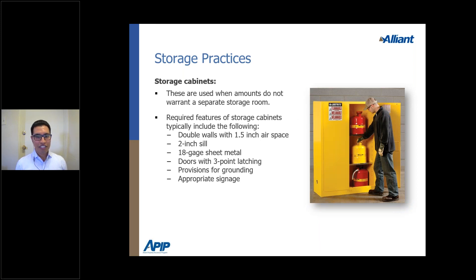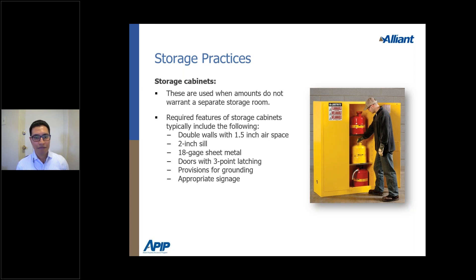Storage cabinets are where flammable liquids, aerosols, and five-gallon safety cans should be kept. Requirements for flammable cabinets include self-closing doors, grounding provisions, and appropriate signage reading 'Flammable — Keep Fire Away.' The purpose of these cabinets isn't to prevent fire from the chemicals inside, but to keep an external fire from reaching inside and potentially causing even greater combustion from the chemicals within.